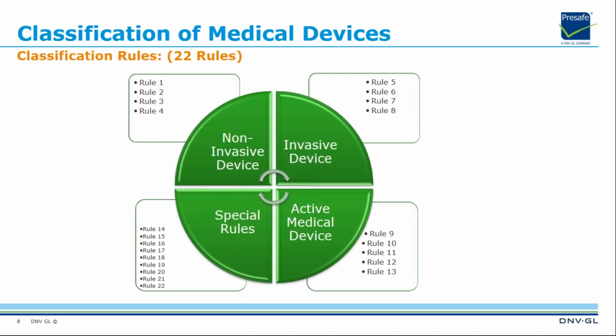What manufacturers can do is examine the MDR classification rules in Annex 8 to determine whether new conformity assessment rules are now applicable to their product portfolio. If so, they should engage their notified body where necessary and take steps to evaluate the necessary timescales involved in implementing this change. In some cases where reclassification has occurred, this may be the first time that such relationships and agreements with notified bodies have been required.